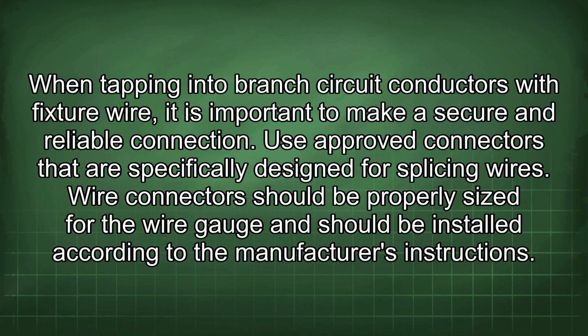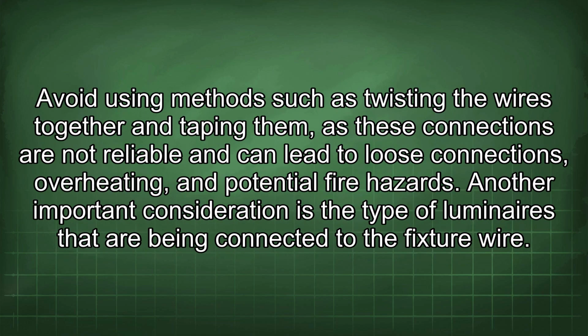When tapping into branch circuit conductors with fixture wire, it is important to make a secure and reliable connection. Use approved connectors that are specifically designed for splicing wires. Wire connectors should be properly sized for the wire gauge and should be installed according to the manufacturer's instructions. Avoid using methods such as twisting the wires together and taping them, as these connections are not reliable and can lead to loose connections, overheating, and potential fire hazards.